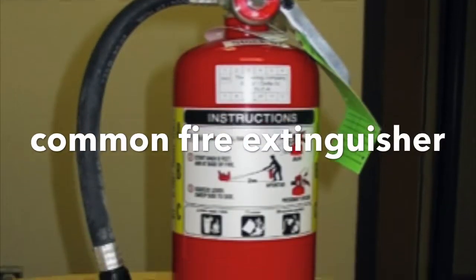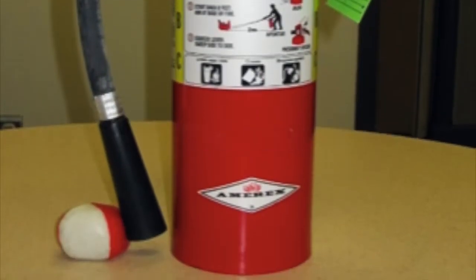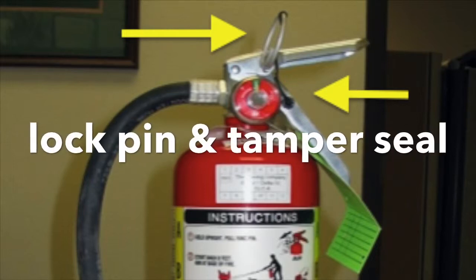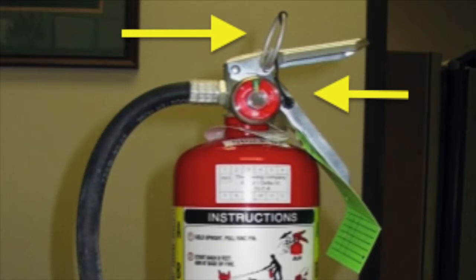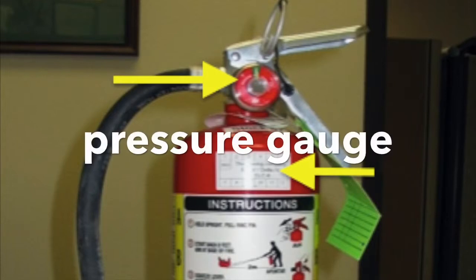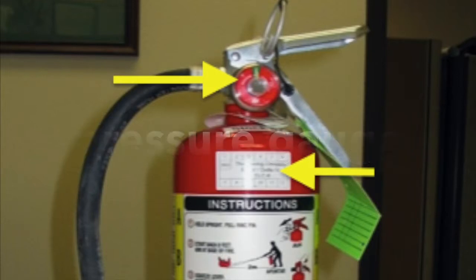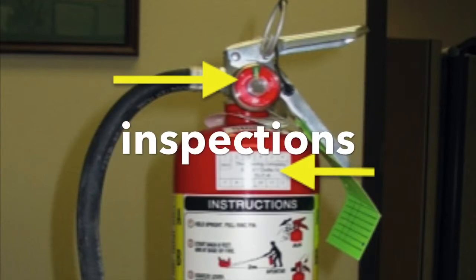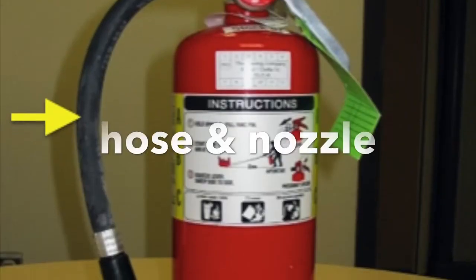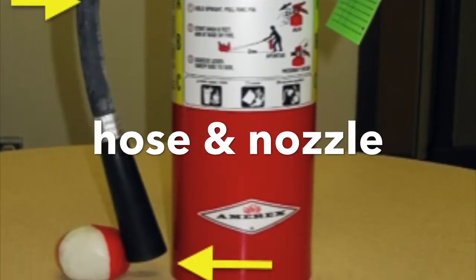Before use, we must check the following on our fire extinguisher. We must make sure that the lock pin and tamper seal are in place, the gauge pressure is in the green or operable range, the monthly and annual inspections have been completed, and the hose and nozzle or horn are unobstructed.